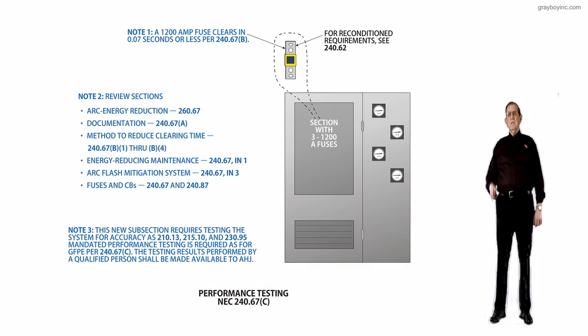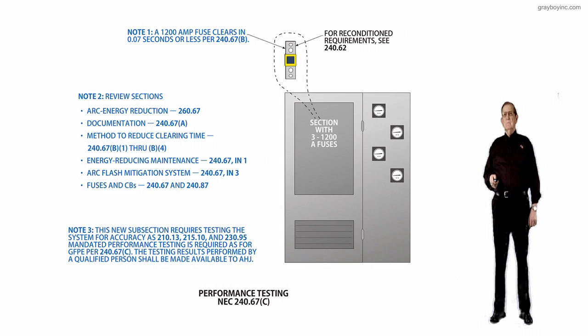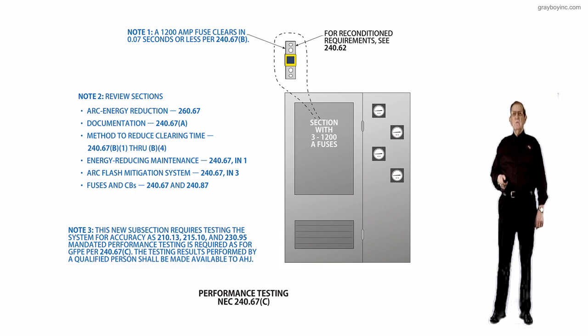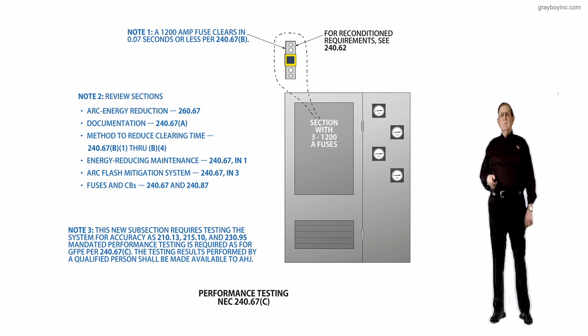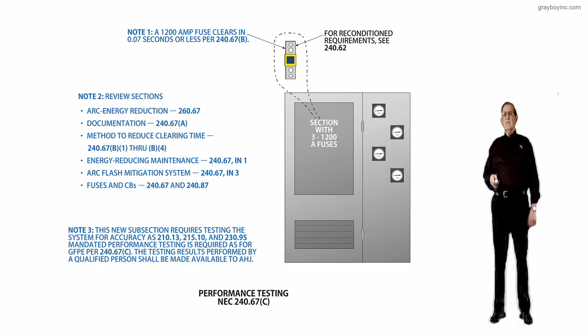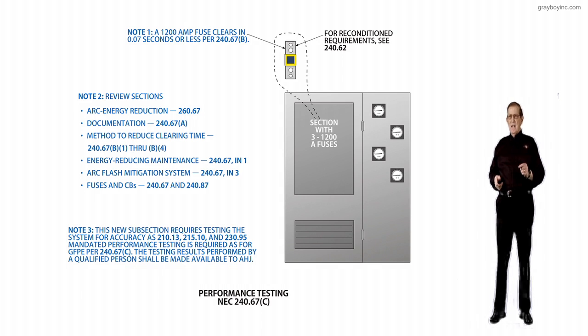This illustration deals with performance testing, 240.67(C). The purpose of the change was to provide a new subsection, and this new subsection has been added to clarify that it is both practical and feasible to require performance testing of arc energy reduction systems at the time of installation.